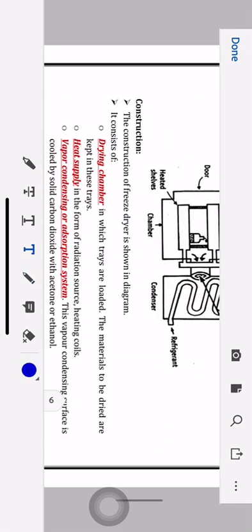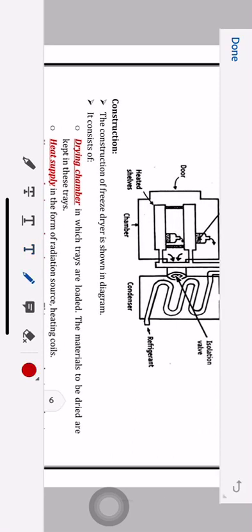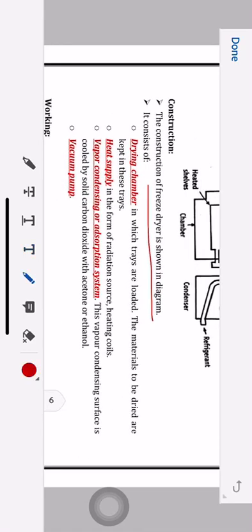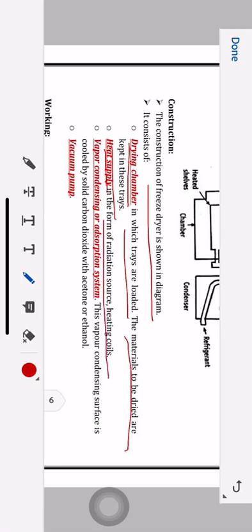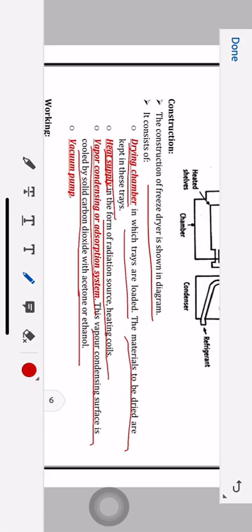Now let's start with the construction. The freeze dryer consists of four important parts. First is the drying chamber in which trays are loaded — the materials to be dried are placed in the trays. Second is the heat supply in the form of a radiation source or heating coils. Third is the vapor condensing or adsorption system — this condensing surface is cooled by carbon dioxide with acetone or ethanol. Fourth is the vacuum pump.